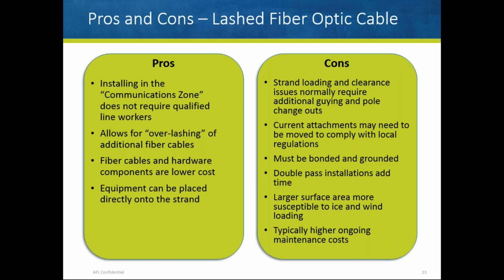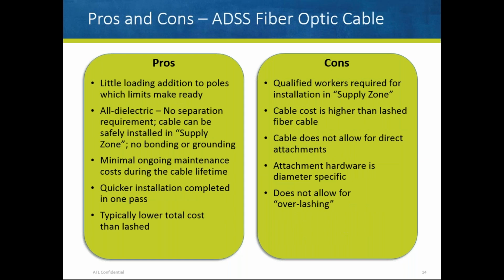Some of the pros and cons of ADSS: the first would really be the loading reduction. In general, ADSS is about 4 times lower loading on your pole than lashed installations in similar environments, which is pretty significant for make-ready and loading onto your poles. There are no metallic components, so the all-dielectric nature of ADSS is really beneficial, especially for the electric utility working with power.